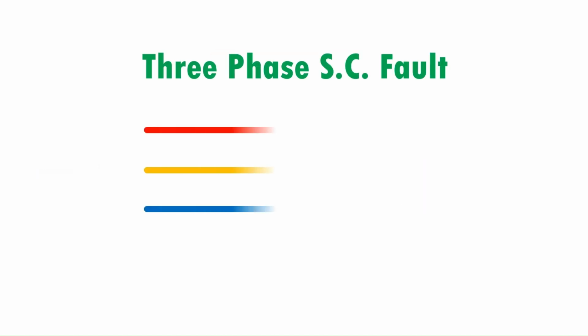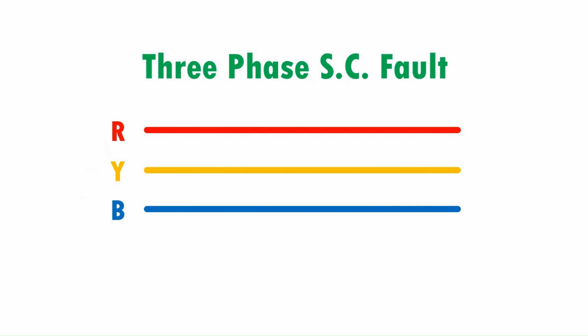In three-phase short circuit faults, all the phases get short circuited. Such type of fault is balanced. That means the system remains symmetrical even after the fault. The three-phase short circuit fault occurs rarely, but it is the most severe type of fault which involves the largest current. And this large current is used for determining the rating of the circuit breaker. The probability of occurrence of such type of fault is less than 1%.